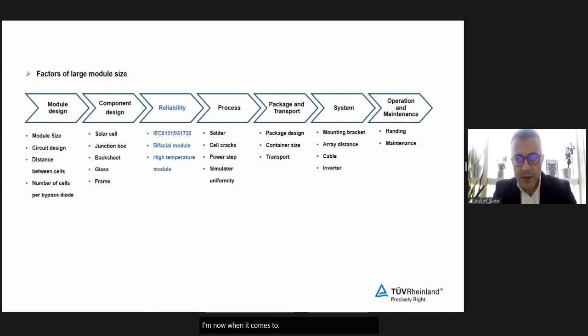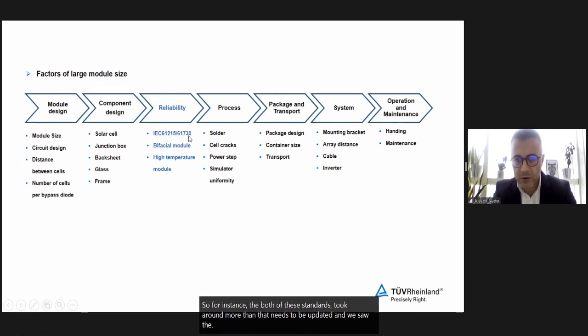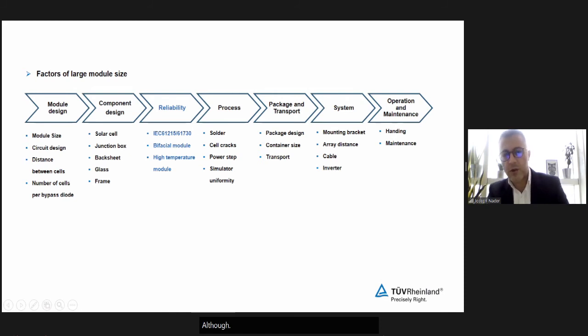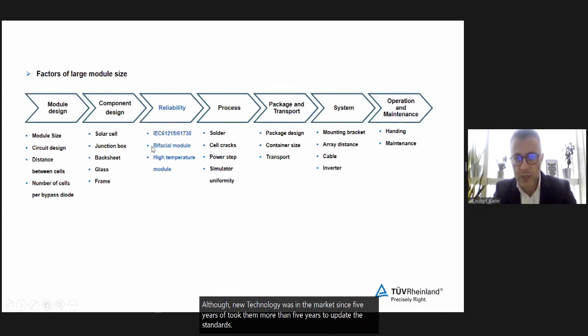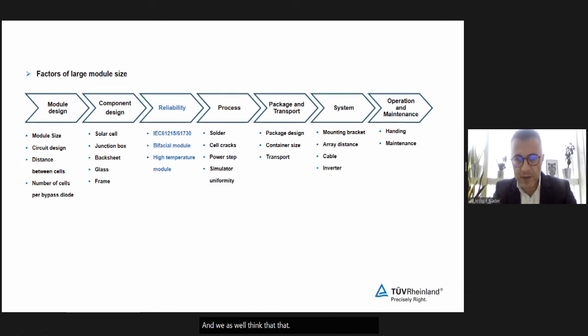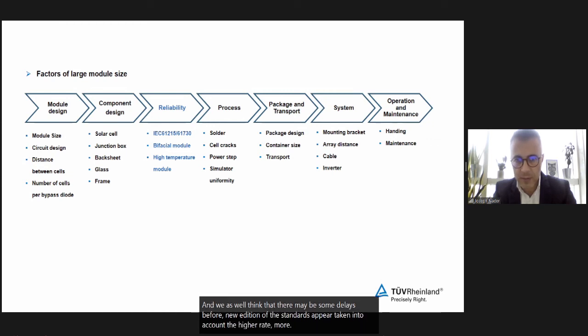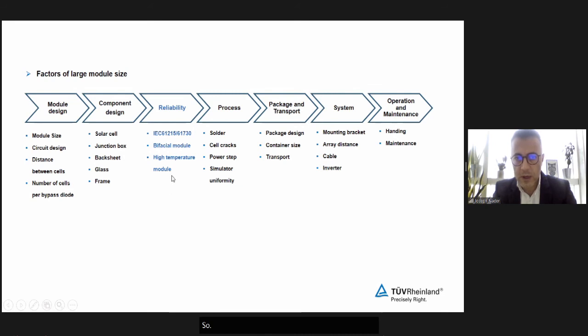Now, when it comes to reliability, we touched a little bit upon the actual standard, and I mentioned that standards usually take time to be updated. For instance, both of these standards took more than 10 years to be updated, and we saw the 2016 version. Although the new technology had been in the market for 5 years, it took more than 5 years to update the standards to account for certain additional tests.